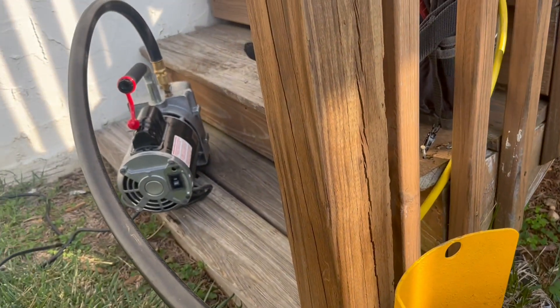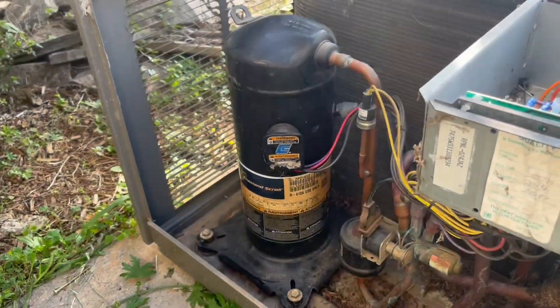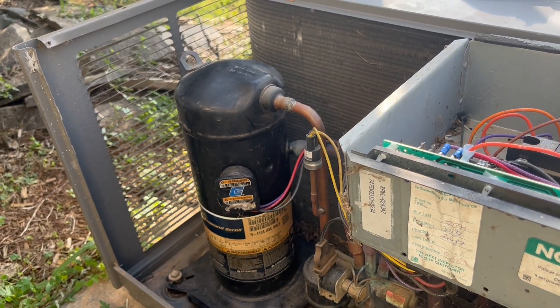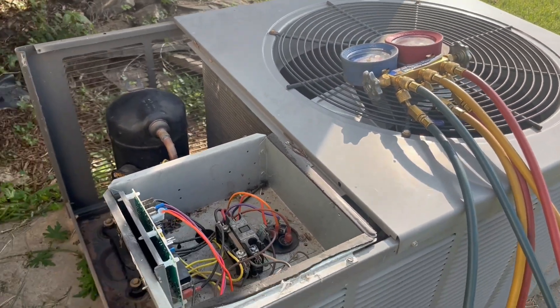I'm pulling a vacuum on my recovery tank because we will be recovering refrigerant from this unit. We have a locked-up compressor, so I will be changing out this compressor on this Rheem heat pump split system. I'm going to take you through the steps.